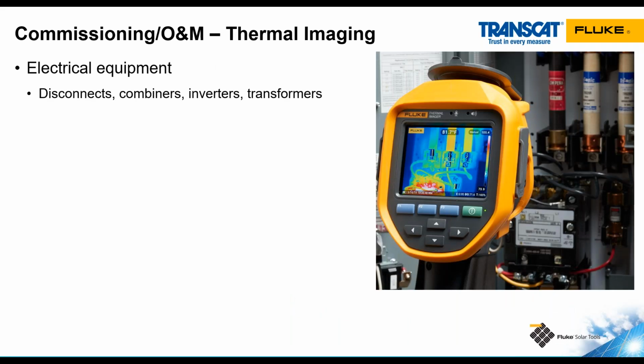Another technique that is used at commissioning and in operations and maintenance is thermal imaging. We can use handheld thermal imagers to look at things like really any piece of electrical equipment like disconnects, our combiner boxes, inverters, transformers, module interconnections, or fuse holders, overcurrent protection devices. On our modules, the most common type of thermography used on modules is aerial thermography. So using a drone with a thermal camera to fly over the array, see if there are any deviations in the temperature of the array.